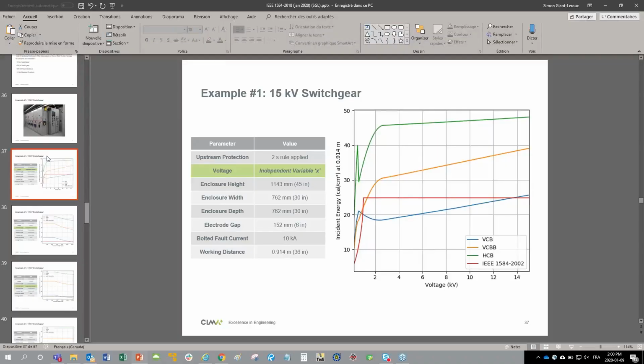Yes. So when we do, for example, a small factory that has a 25 kV to 600 volt transformer, and we check the incident energy on the main breaker of the 600 volt switchgear, we always put 2 seconds, because the utility can change their fuse, the fuse upstream of the transformer, anytime they want, and they can put a fuse that's slower than the one in your study, and then your arc flash label doesn't work anymore. So that's why we use 2 seconds.